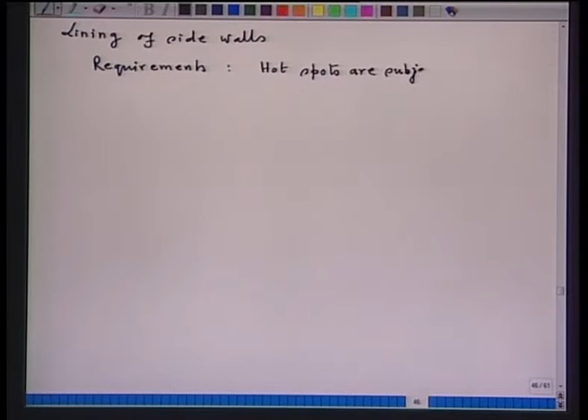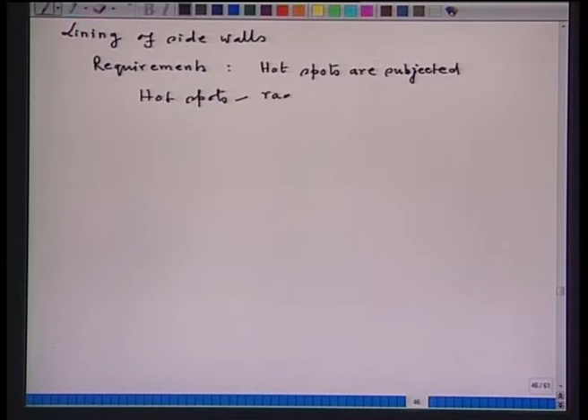Now, some of the lining requirements of refractory for side wall. Because the electrodes produce the arc, and the radiation of the arc, you have 3 electrodes, 3 hot spots could be formed on the walls of the furnace. So, the hot spots are subjected to severe conditions.